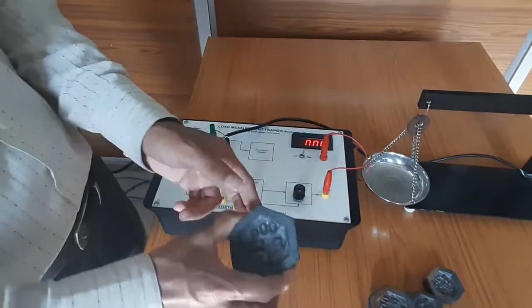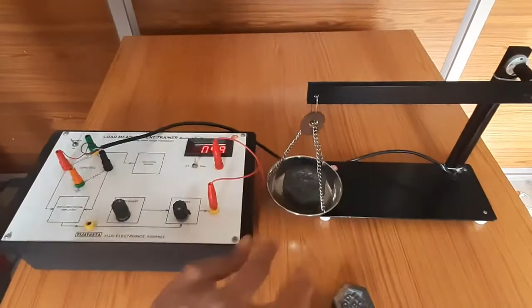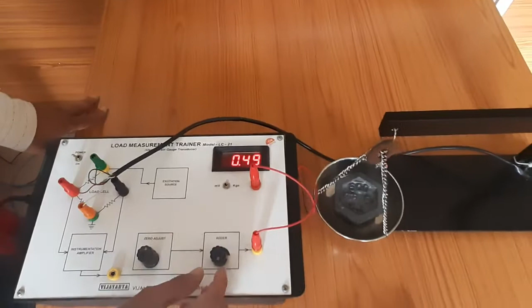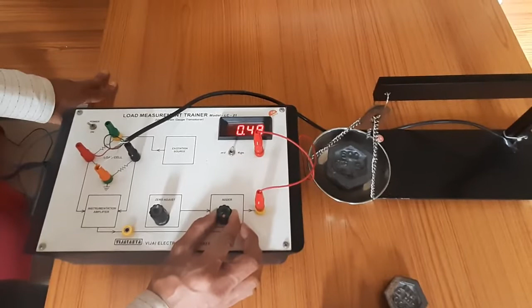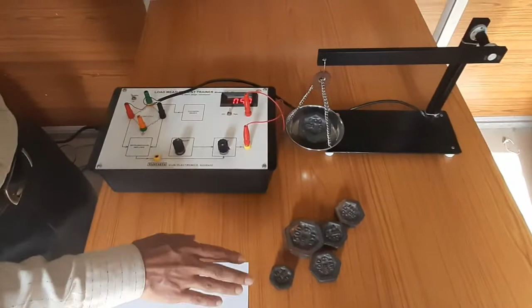Now I have this 500 gram weight. I put it here. I see that it is showing 0.49. So there is some calibration error. Using this adder, I can change it, because I know that it is 0.5 kg. So I adjust it. Now it is showing 0.5. So I have calibrated it using this weight. Now I can use it to measure all the weights.